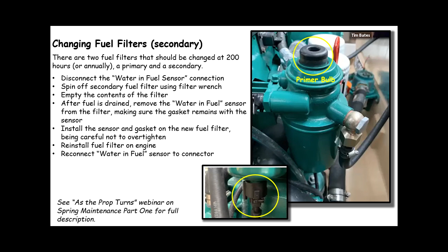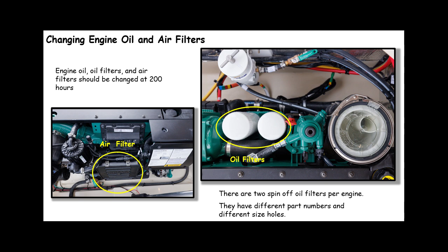The engine oil filters and air filters should be changed every 200 hours. The air filter is in this black canister with the two metal latches, shown in the left-hand picture. There are two spin-off oil filters, and those have different part numbers and different hole sizes. So when changing your oil, make sure you get one of each.